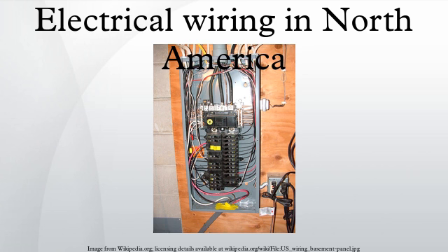Many wires are rated both THWN and THHN, and are suitable for use in dry locations up to 90 degrees Celsius, or wet locations up to 75 degrees Celsius. See also, American wire gauge, twist-on wire connector. References. External links, the NEC at nfpa.org, Summary of NEC Color Code.